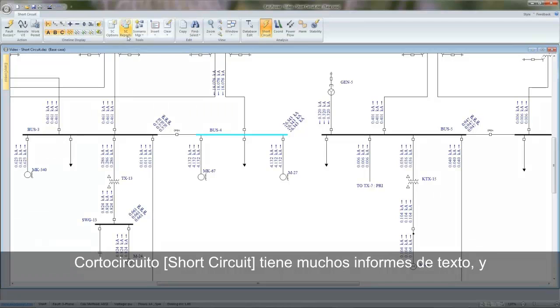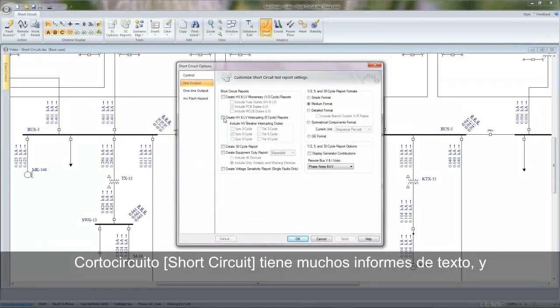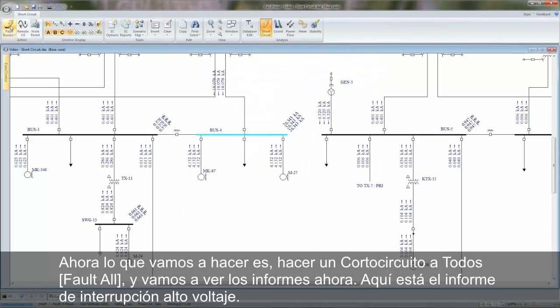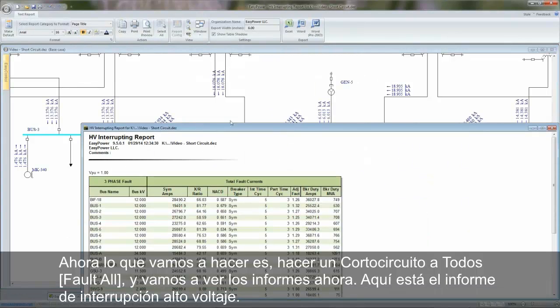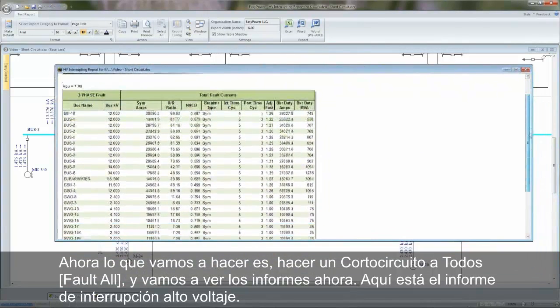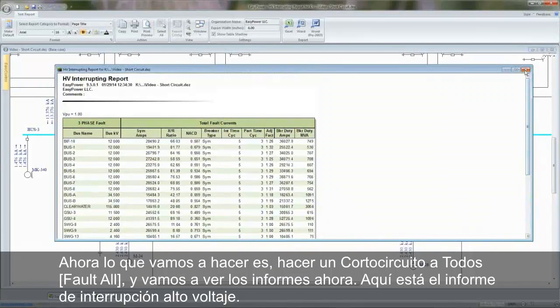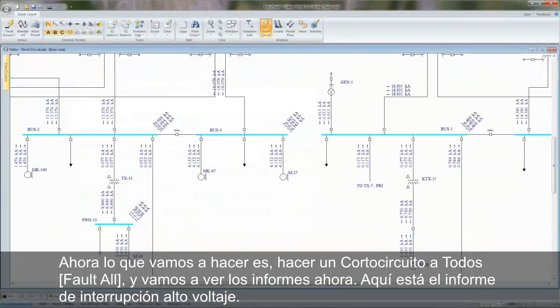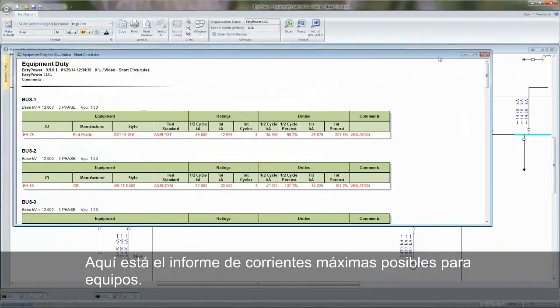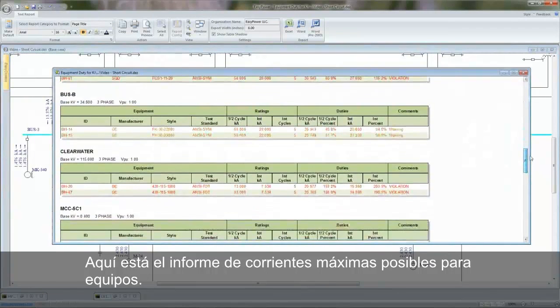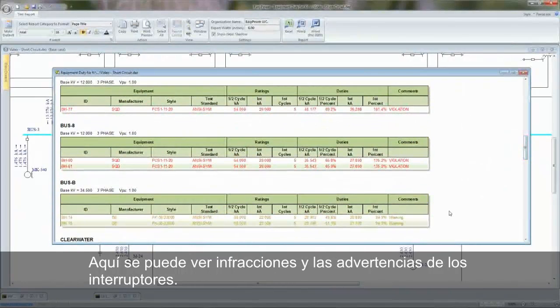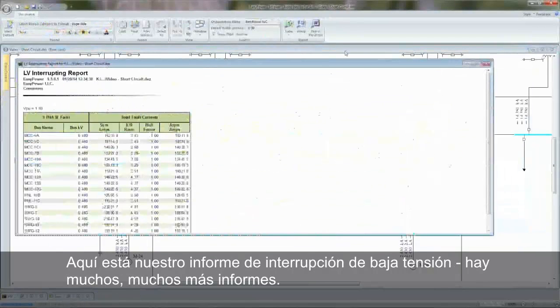Short circuit has many text reports, and we can use many of these different text reports to show different types of short circuit results. Now what we're going to do is do a fault all, and we're going to see the reports now. Okay, so here's the high voltage interrupting report. Here's the equipment duty report. Here we can see violations and warnings of breakers. Here's our low voltage interrupting report.